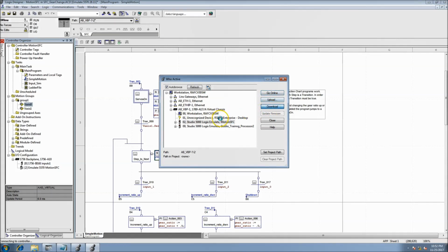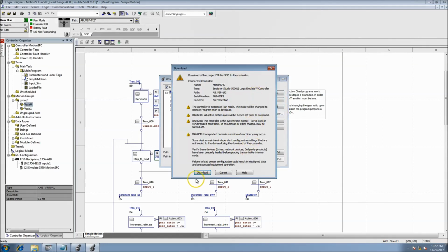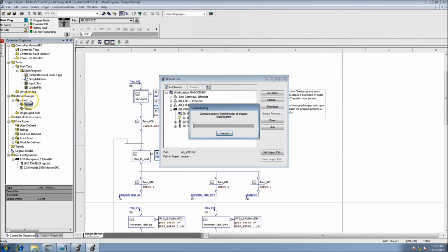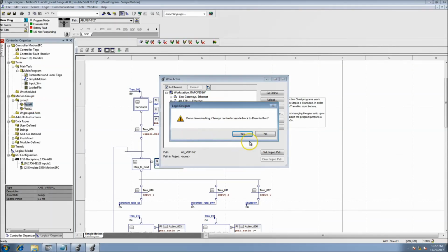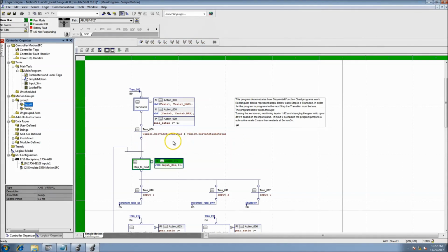They won't do anything until they cut on. If the motion group is not happy, it's not going to cut anything on. It's not going to initiate any commands. It'll try, but it won't do anything. It's just something you learn with servos.